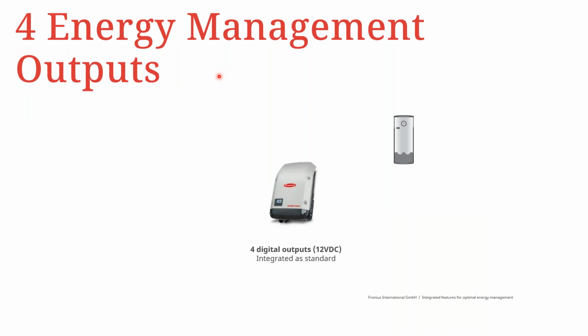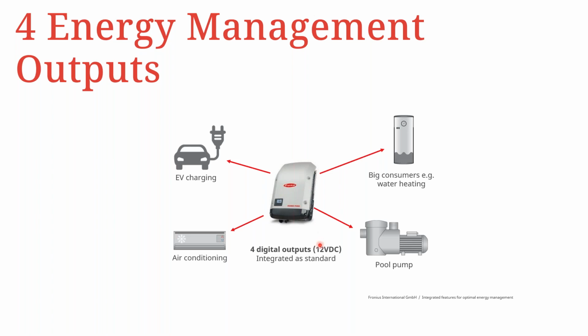So when it comes to the management using the 4 digital IOs, as you know, every Fronius inverter has these digital IOs integrated. So if it's the Snap inverter with the Data Manager, then you have these 4 digital IOs, which give out a 12-volt DC signal. And this is integrated as standard, like I said, provided you have the Data Manager within the inverter. So with these 4 energy management outputs, you can control things like an EV. You can also control air conditioning and then a pool pump, in addition to other big consumers like water heaters.